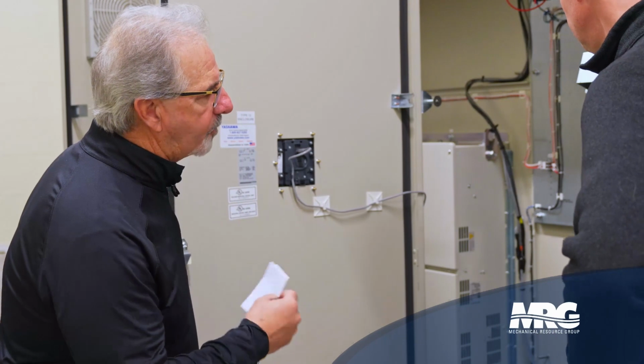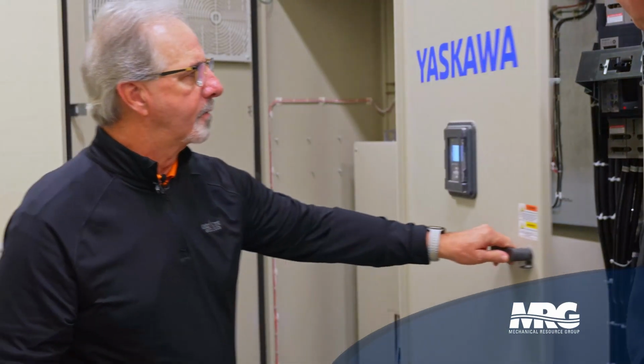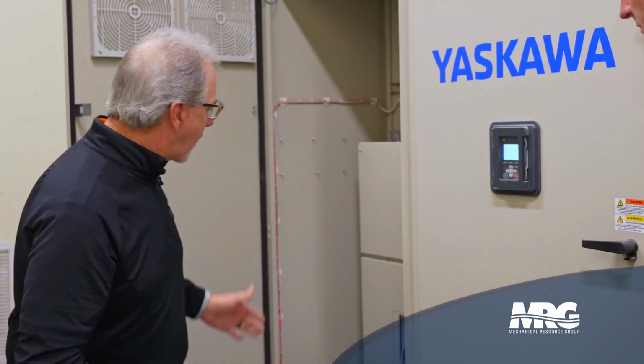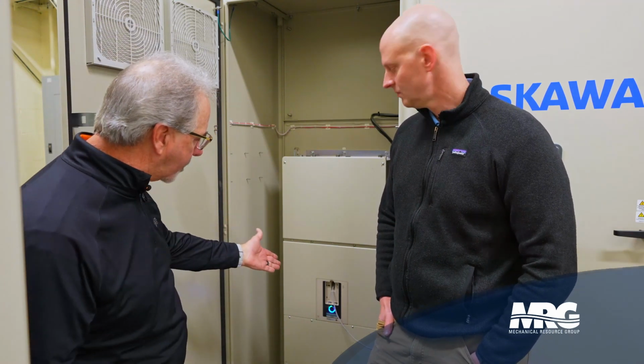Okay, so now if we come over here and we shut this door, over here is the drive itself. So like I was telling you, Yaskawa does a really good job of informing its operators of the condition of the drive without really having to interact too much. So if you look at the screen down here on the bottom, Yaskawa came out with this year, it's the blue smiley face. Yeah. If you see a blue smiley face, that means that the drive is operating the way it wants to. When you see the green light that's up above it, that means that drive is actually running.